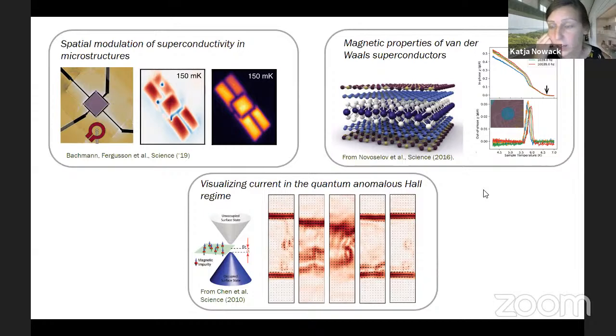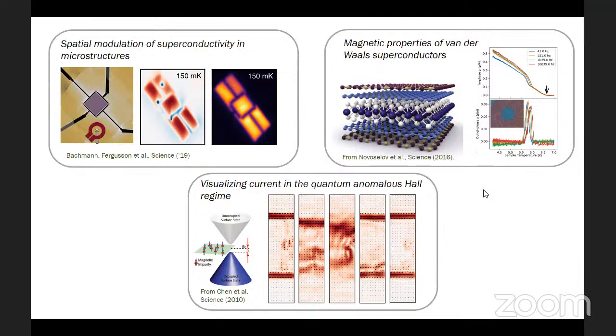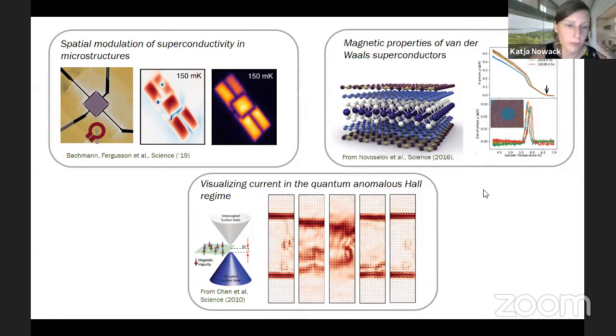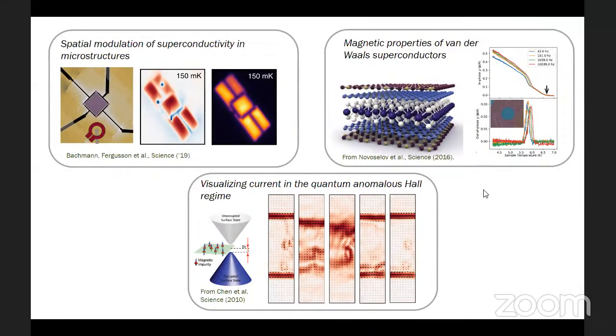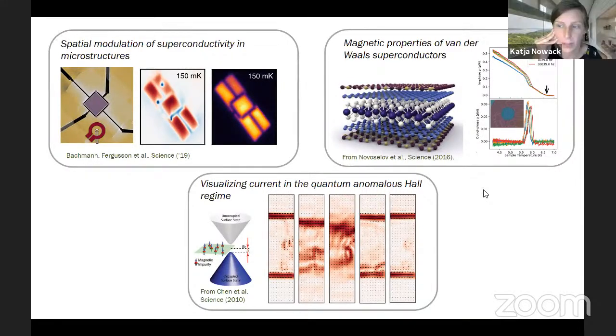our squids actually have a lot of topography. If you were to look at them from the side, they have a lot of terraces and steps and whatnot. And so if I keep all that extra circuitry, there's no way for me to bring the sensitive area closer to the sample than maybe within 300-400 nanometers. We do have some squids with that size of pickup loops, some with 300 to 400 nanometer diameter pickup loops.